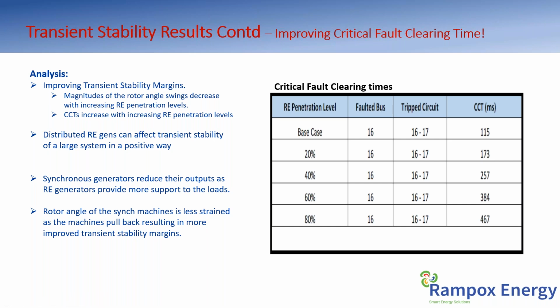So if your critical fault clearing time is increasing like this, it's a good indication that your stability margins are improving. Why? Because that means you can tolerate longer faults. So that's another thing to remember: the more you can tolerate faults that last longer, the more your stability is improved. When we use this index of critical fault clearing time, if this time gets close to our normal standard breaker or protection clearing time, which for the transmission system would normally be around 100 milliseconds or so, I think, for the ESCOM system.